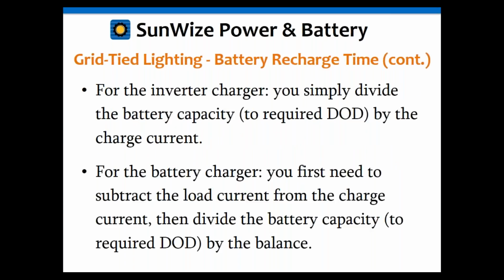Okay, so for the inverter charger, you can simply divide the battery capacity, and that is to the depth of discharge required. Again, since your LVD is going to be at, say, the 80% discharge point, you only need to worry about 80% of the battery capacity. So you can simply divide that by the charge current from the charger, and that gives you a pretty good approximation of your recharge time. Now, if all you have is a battery charger, then you need to subtract from that charger output first the load current, because remember, you need to support the load. So if you have, say, a 25 amp charger as an example, and your load is 5 amps, then you only have 20 amps remaining to recharge the battery. So then you would take whatever that remaining is, and then divide the battery capacity by that to get your recharge time.